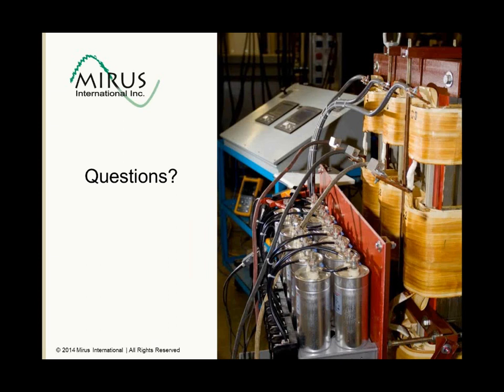This is often the case in hospitals, where obviously you have to have that backup generation, and typically they're running into harmonic problems when they're running on backup, which is the last thing they want to be dealing with when they're dealing with a power failure. But when you treat the harmonics, you have to make sure that the generators can handle the capacitive reactance at light loads. And that's why it's important to use a filter that has low capacitive reactance. If you use a filter with low capacitive reactance, it absolutely can be applied both on utility and on backup generator.